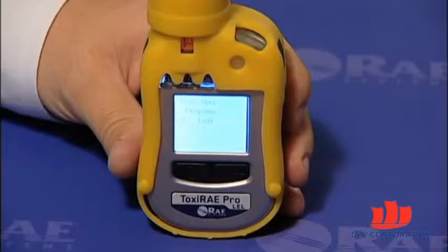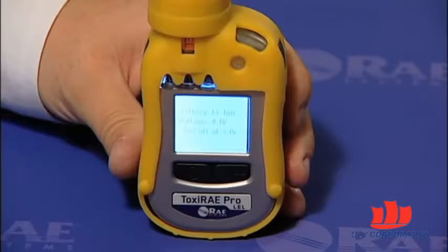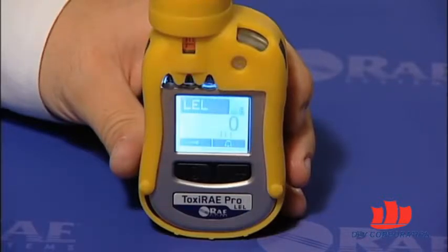If you have installed a sensor that's not supported by the instrument, you will get a wrong sensor message. In that scenario, you have to remove that sensor and replace it with a sensor that's supported on the instrument. If the boot up cycle completes successfully and you get to the main measurement screen, you have done a good and proper job of replacing the sensor on your ToxiRAE Pro.